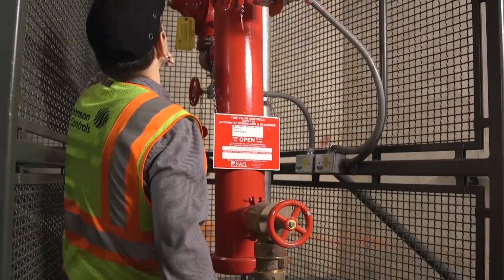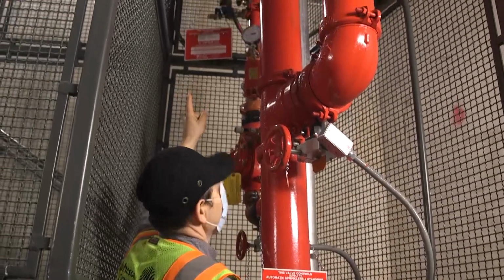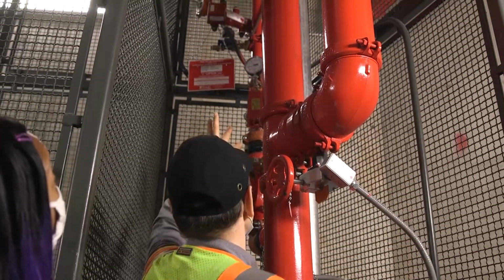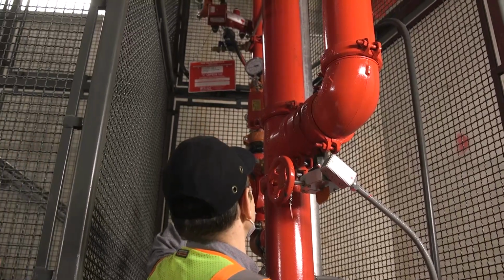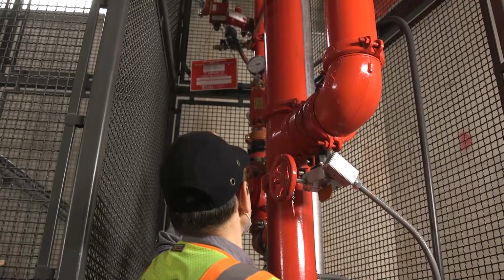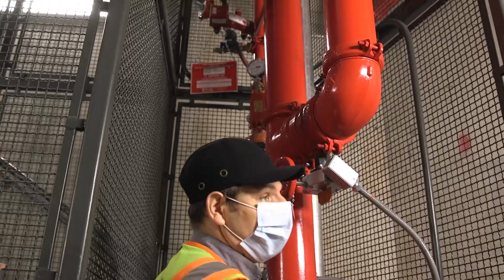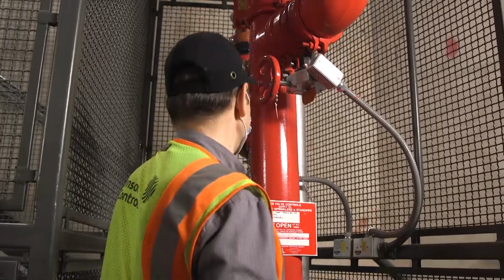And that device, it's a corrosion monitor. That up there, it's a corrosion monitor, so anytime that supervisory comes, because it comes as a supervisory abnormal, that means it needs to be reset because dirty water was inside the pipe and that activated the corrosion monitor.